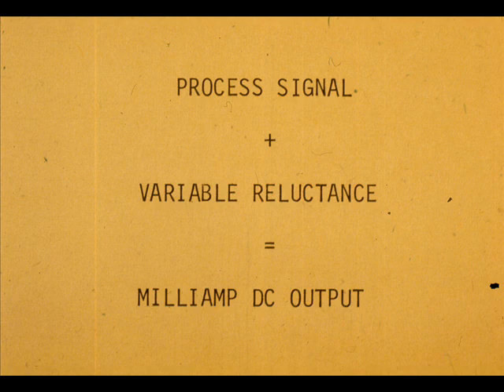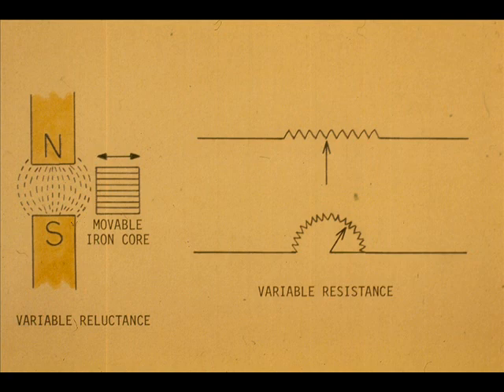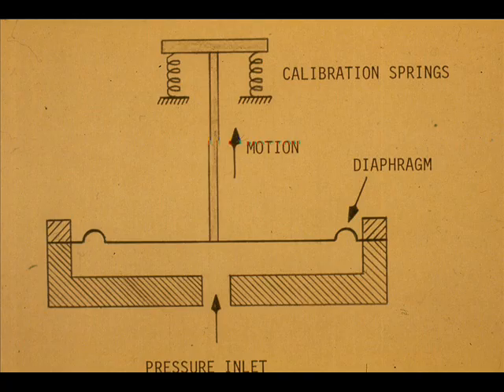The motion and force balance types to be studied rely on the principle of variable reluctance to convert process signals to milliamp DC signals. Variable reluctance in a magnetic circuit is comparable to variable resistance in an electrical circuit. In the motion balance type transmitter, the process pressure or differential pressure is opposed by a calibrated spring.